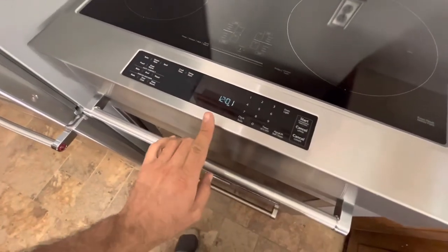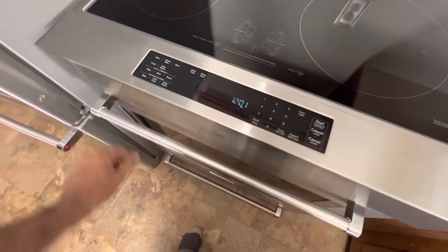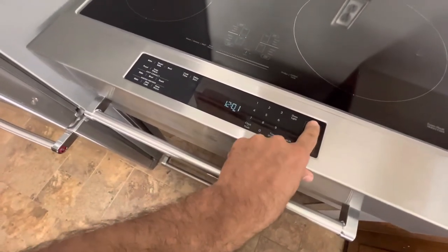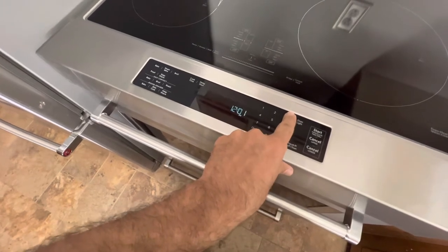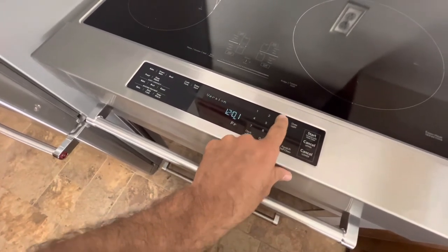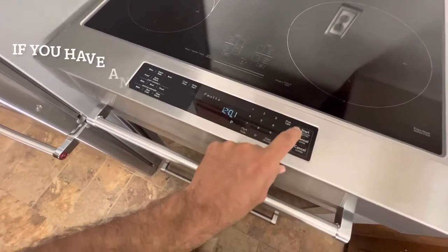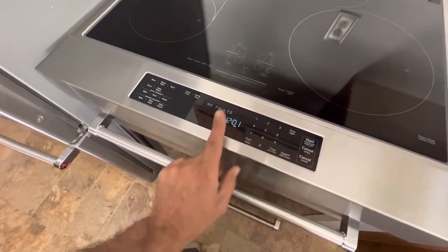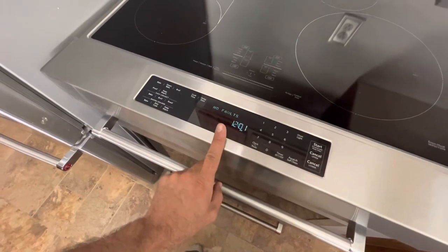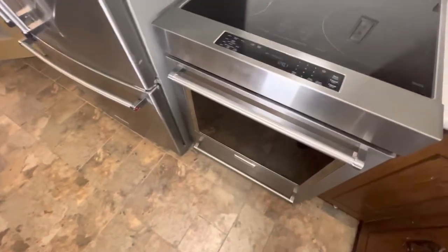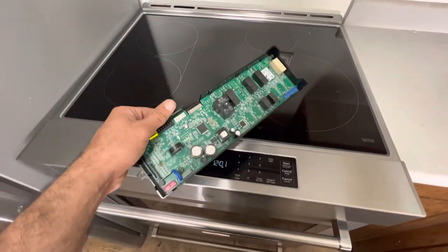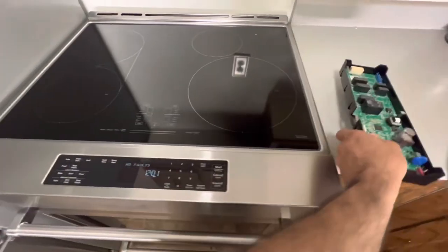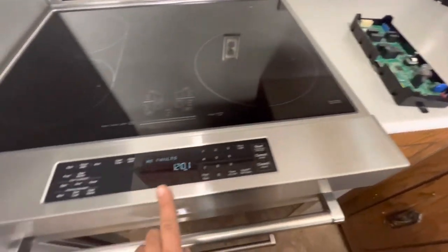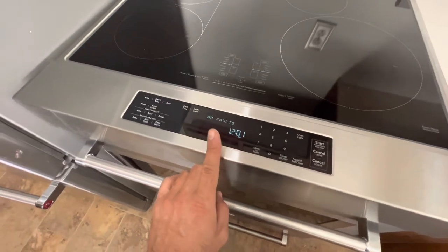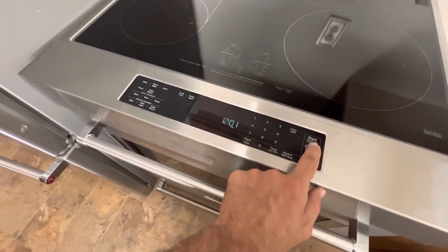So now after the control board installation, I'll go back on diagnostic and clear the error codes if there are any. No faults. Why don't we have faults? Because all the faults and error codes get saved in the control board. So I removed the old one, and we got a new one. I double checked it just to make sure everything is safe here.